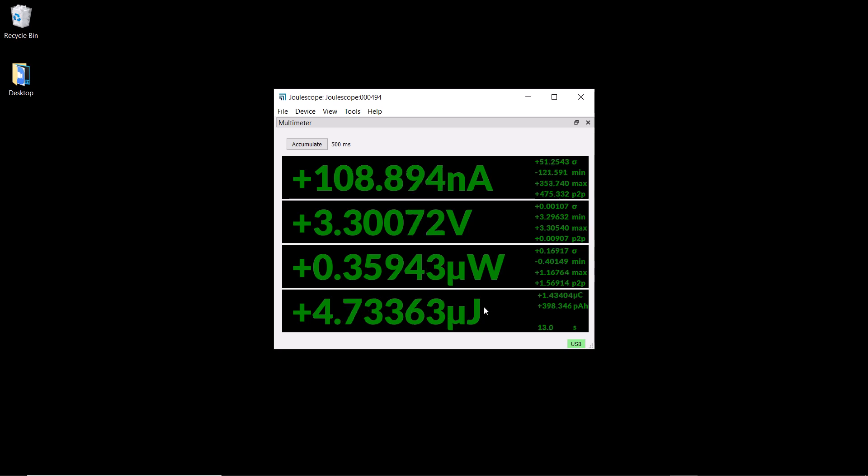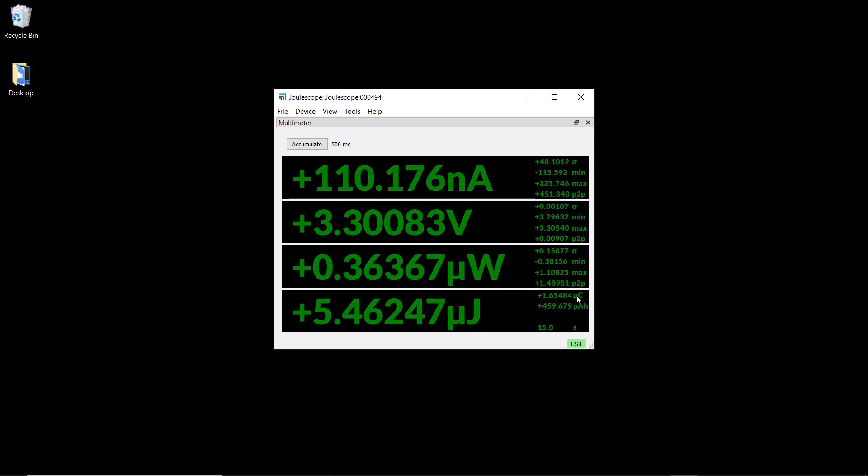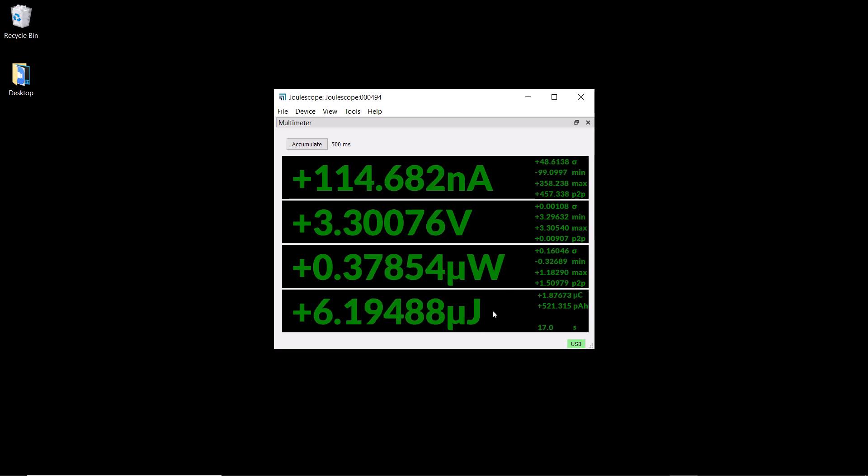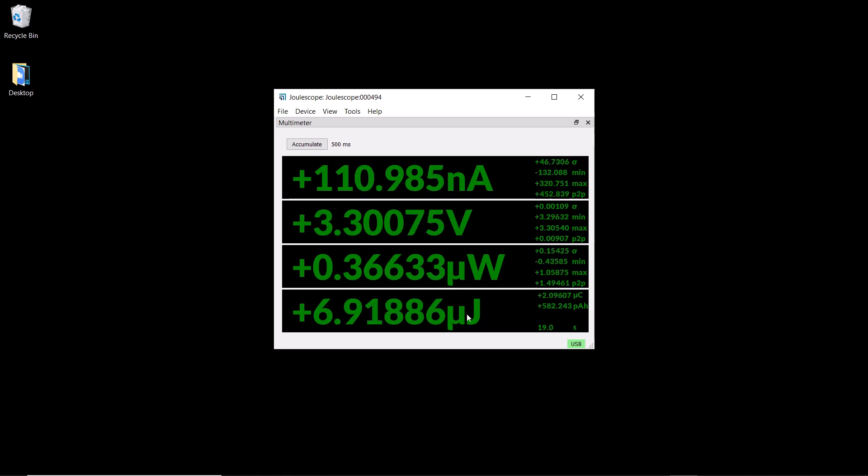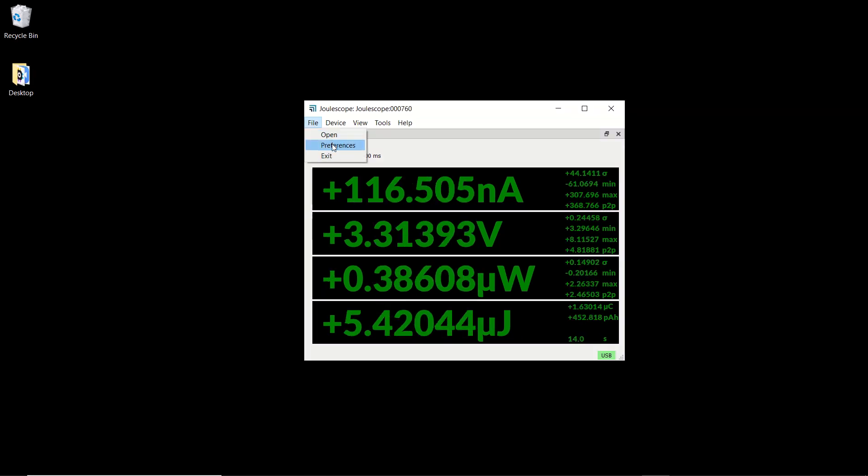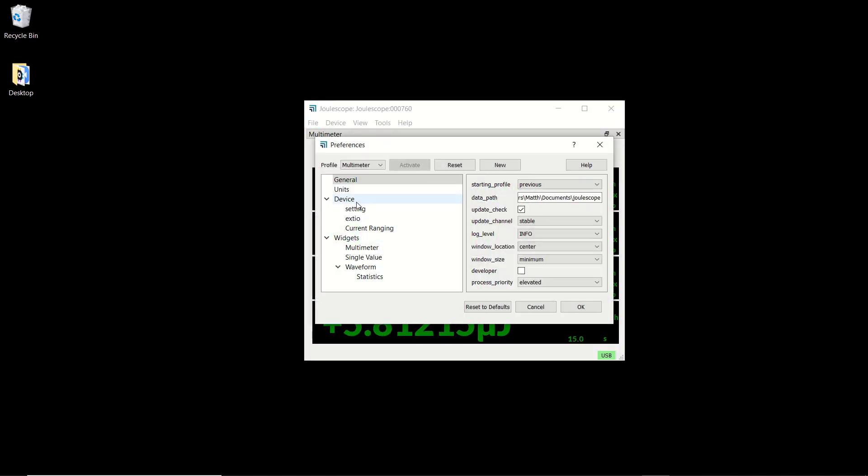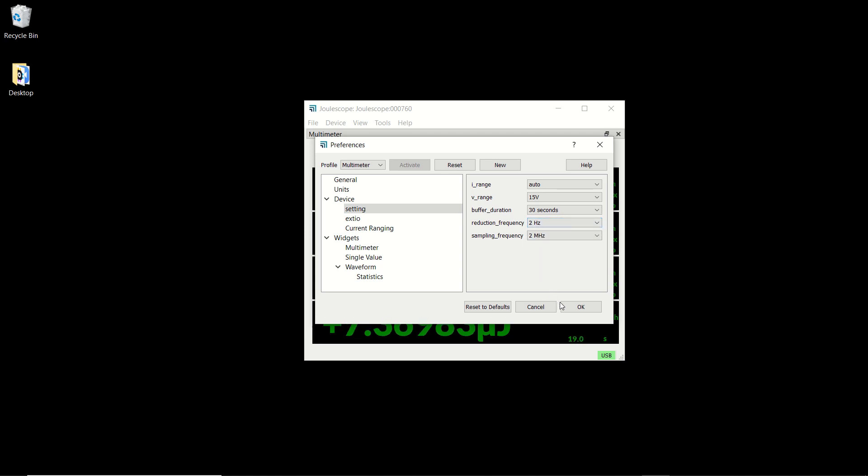The energy display also shows charge both in coulombs and amp hours along with the integration duration for both energy and charge. It defaults to a 2 Hz update rate, but you can configure it from 1 Hz to 100 Hz.